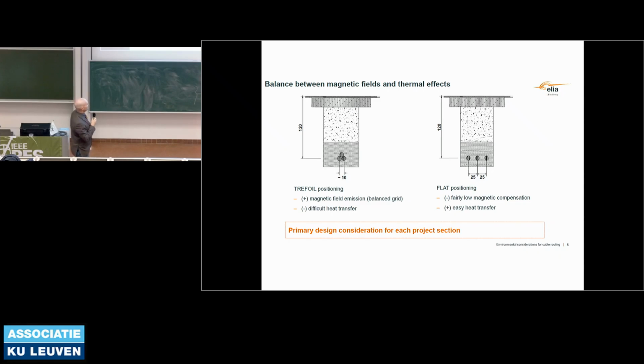Then you would go to the flat positioning. Flat positioning, as you'll see in the slides after, is way worse for radiated magnetic fields, but you get better heat transfer. So for each project section, it's not that we say a new cable line from substation A to B will only use trefoil or only flat. No, we would partition the whole routing and see for which section the best solution can be found.